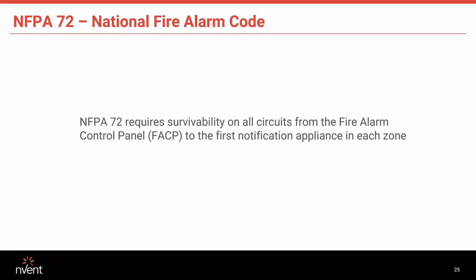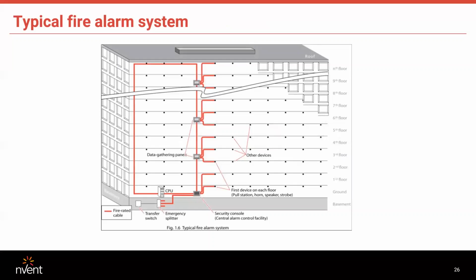You do have, as I mentioned before, NFPA 72, which requires survivability on all circuits from the fire alarm control panel to the first notification appliance in each zone when you have a partial evacuation system. So again, from the fire alarm control panel to the first notification appliance in each zone when you have a partial evacuation system. What is a partial evacuation system? Generally you find them in high-rise buildings or buildings with several wings. So for example, they may say floors 4 and above, you stay put, floors 3 and below, you evacuate. So when you have a partial evacuation system, the circuit from the fire alarm control panel to the first notification appliance in each zone must be fire rated for a period of 2 hours.